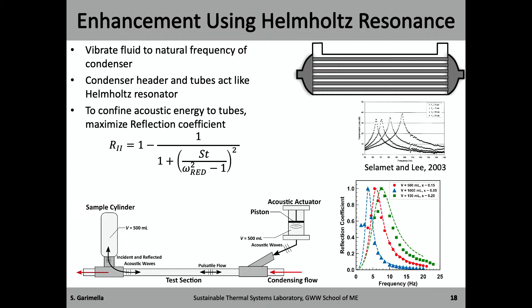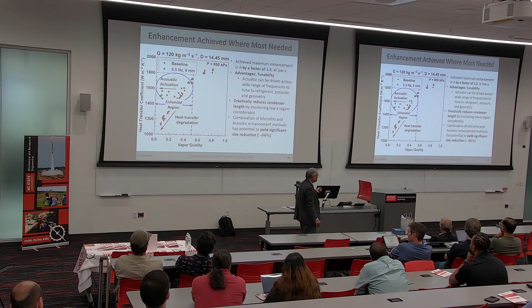What this does is reduce the size needed at the tail end of the condenser, which usually takes so much surface area to accomplish condensation. Whereas the heat transfer coefficient would normally keep dropping at high vapor qualities, making it take a long tube to complete condensation, with this tunable enhancement you keep the coefficient high and reduce the condenser size.